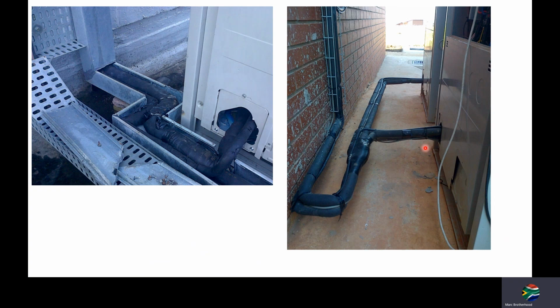Totally unnecessary. And also very important, remember that there have to be pipe supports here. When the units run, the pipes experience a lot of internal momentum running inside of them, plus the weight of the refrigerant. And with time, gravity is going to cause these pipes to drop and bend. So you have to support this in protected cable trays.